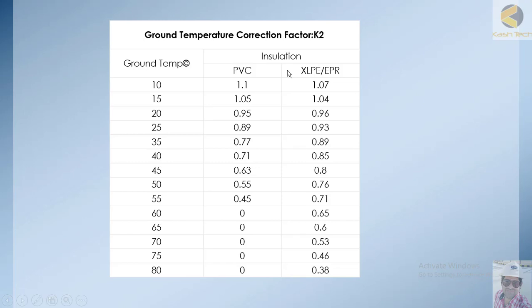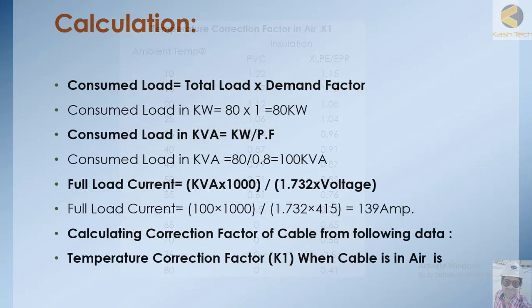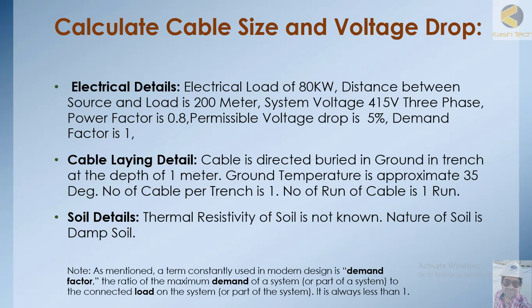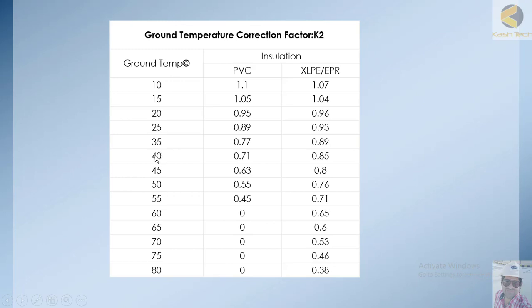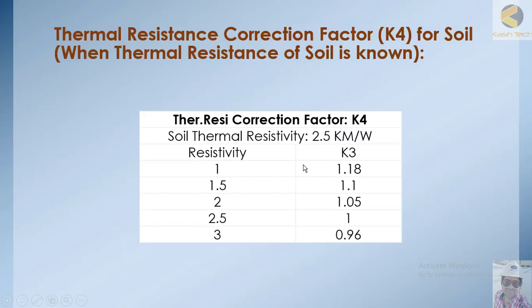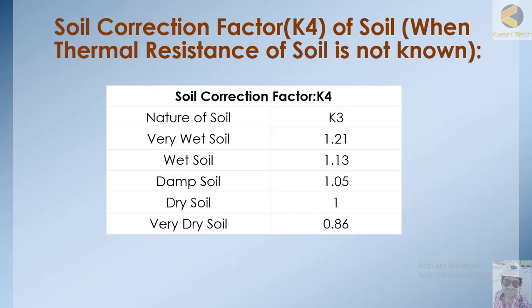Similarly, we have a ground temperature correction factor. The ground temperature is 35 degrees centigrade. Note that ambient temperature is normally taken as 40 degrees centigrade in hot areas. For the soil resistivity correction factor K4, since we don't know the resistivity of the soil but the soil condition is wet or damp, we take a correction factor of 1.13.